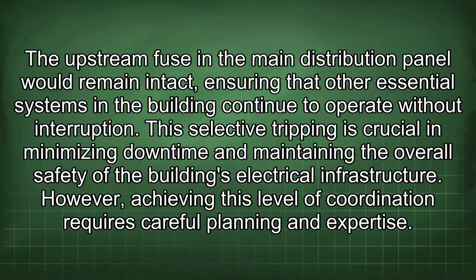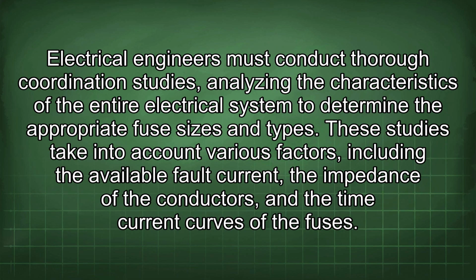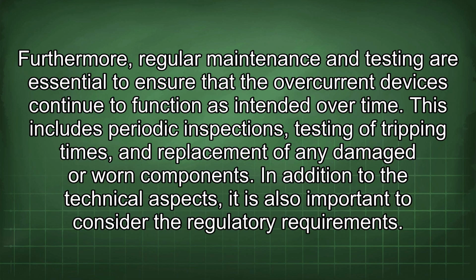However, achieving this level of coordination requires careful planning and expertise. Electrical engineers must conduct thorough coordination studies, analyzing the characteristics of the entire electrical system to determine the appropriate fuse sizes and types. These studies take into account various factors, including the available fault current, the impedance of the conductors, and the time current curves of the fuses. Furthermore, regular maintenance and testing are essential to ensure that the overcurrent devices continue to function as intended over time. This includes periodic inspections, testing of tripping times, and replacement of any damaged or worn components.